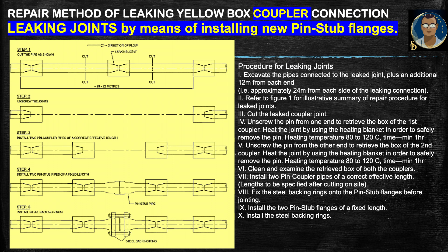The second procedure covers the leaking joint by means of installing new pin-to-stub flanges, which is for the coupler type of yellow box connection. Similarly, we excavate the pipes connected to the leak joint plus an additional 12 meters from each end — approximately 24 meters from each side of the leaking connection. Cut the leaked coupler joint as step one, then unscrew the pin from one end to retrieve the box of the first coupler, heating at 80 to 120 degrees centigrade for a minimum of one hour.